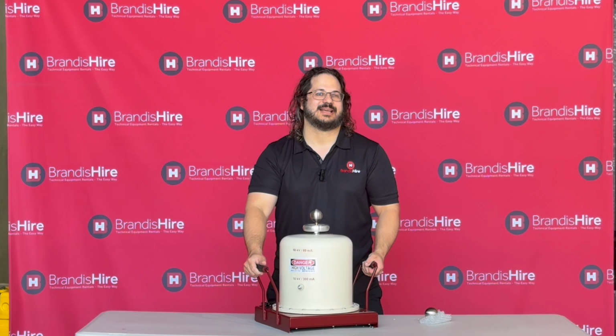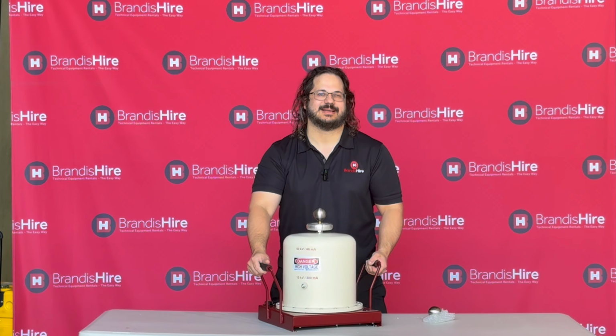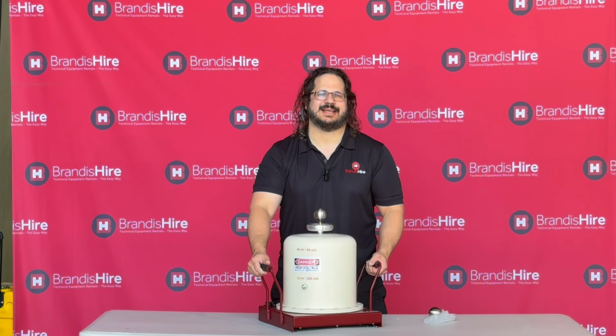So this unit goes all the way up to 50,000 volts and puts out up to 60 milliamps. However, one thing to note with this guy, it's got a 10 kV tap, and that 10 kV tap can go all the way up to 300 milliamps. So if you've got a highly inductive load that's a low voltage, it makes the perfect set to go with it, because you'll get enough power in there to be able to punch through the load.